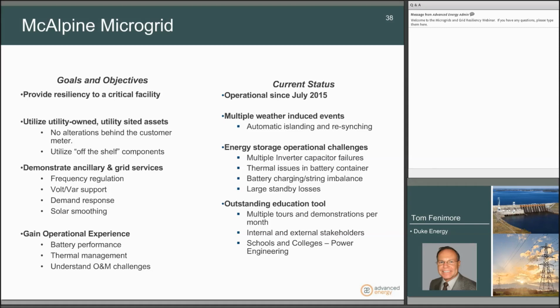We had wind-induced events that caused the voltage to drop on circuit 2414 at that substation. Doing what it's supposed to do, the system disconnected from the grid and ran the fire station on battery, with the energy storage system providing all the power needed for a period of time. When the weather calmed down and the circuit voltage stabilized, we reconnected and resynchronized back to the grid.